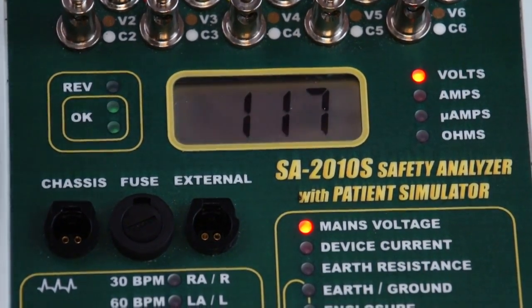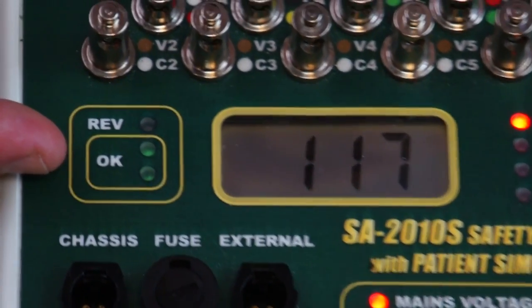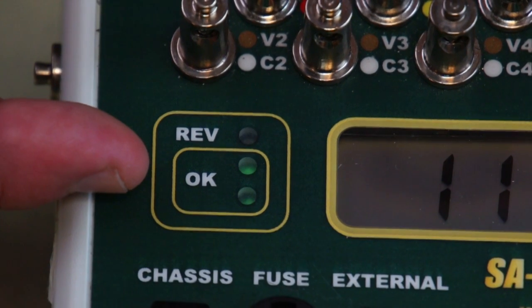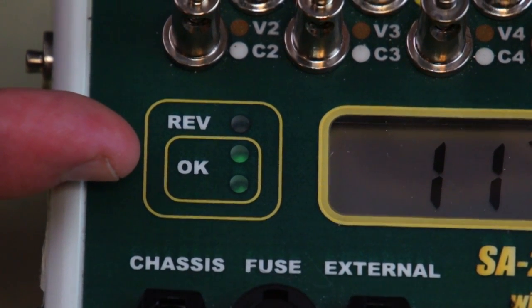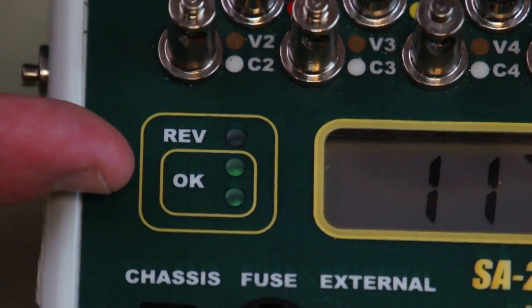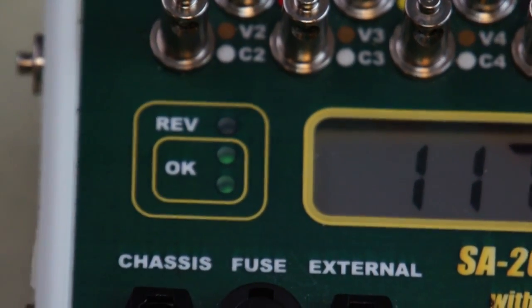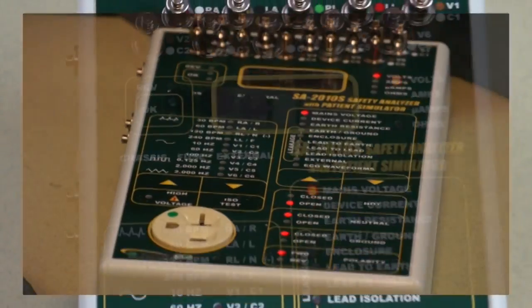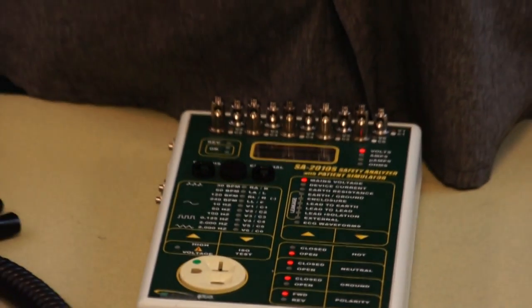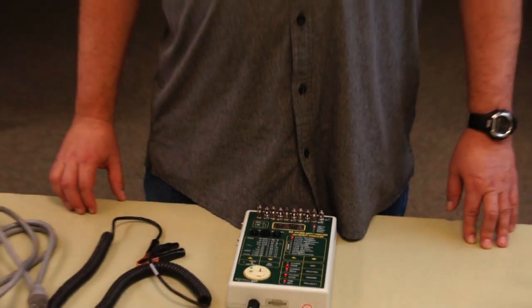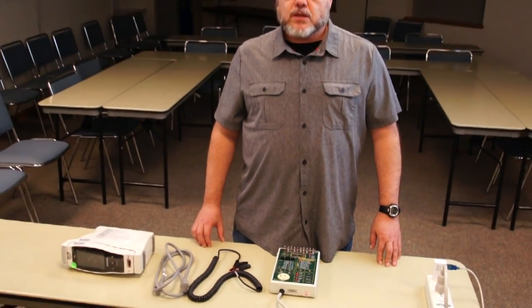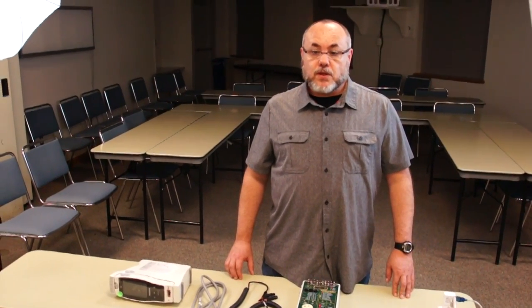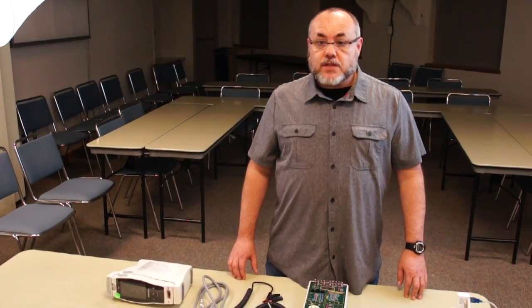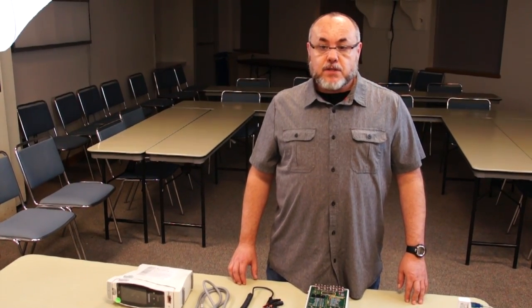There are two LEDs on the left side of the display that show the condition of the line itself. They show whether the polarity and the ground are okay. It is critical that we make sure this is correct before we go any farther, because if there's a problem here, then the rest of our test isn't going to give us true results. There's a table of the different LED possibilities and their meanings on the back of the analyzer itself.